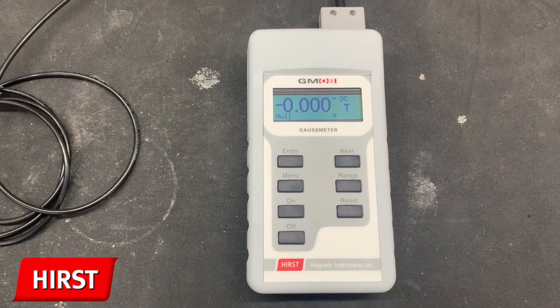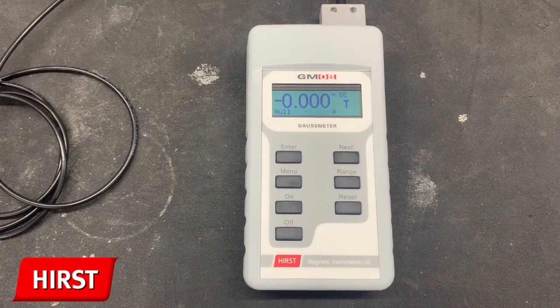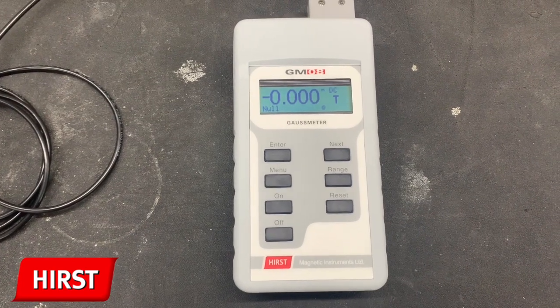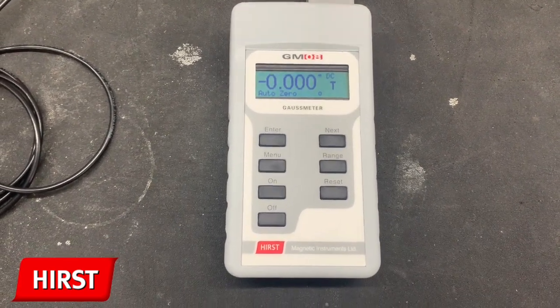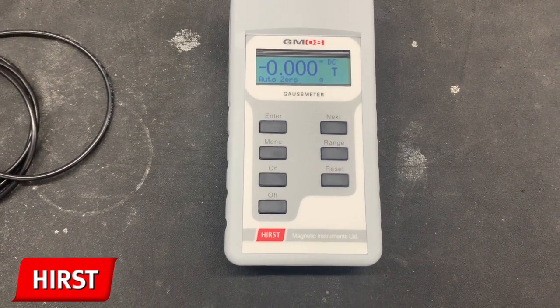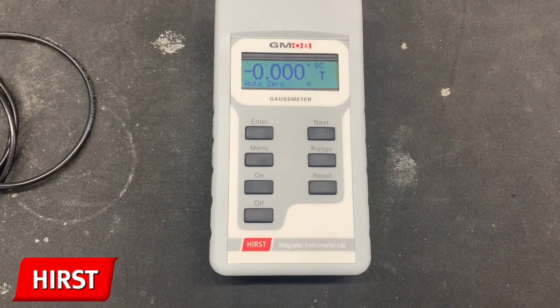Finally, the utility submenu. The first option is the null function. This allows the user to quickly null the GM08 and the probe, which is useful for taking very sensitive readings. The auto zero function allows the user to perform an auto zero calculation using the zero gauss chamber that is equipped with the GM07 and GM08.